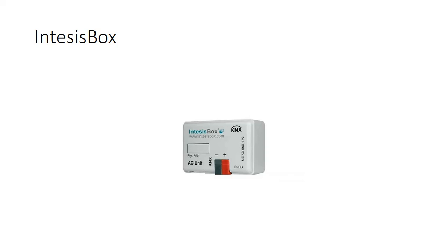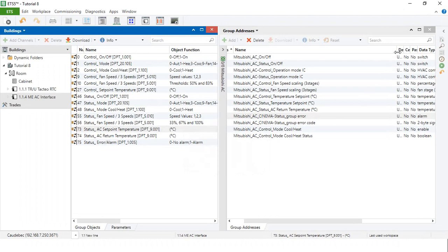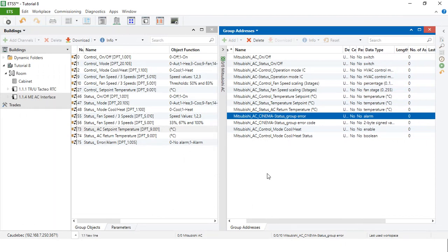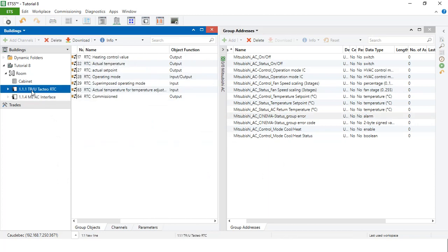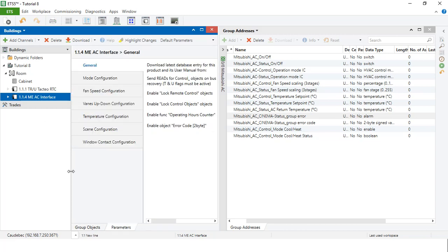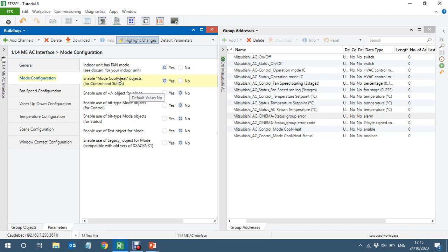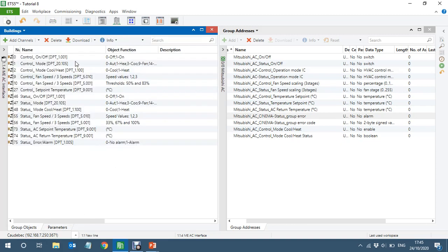Let's go back to the programming. I have already created the group addresses and added the ABB RTC and AC interface. In the parameters of this device, under mode configuration, I have enabled the heat/cool object. What I want to do is link this with the RTC heat/cool, and it will automatically set the AC to heat or cool mode.